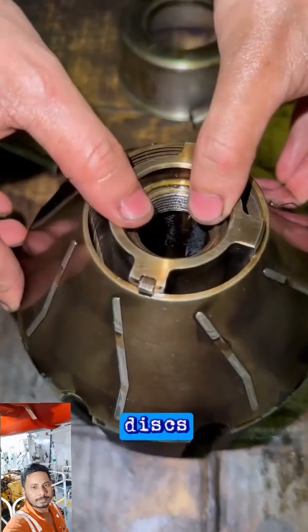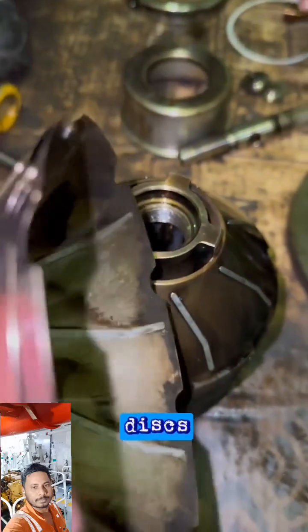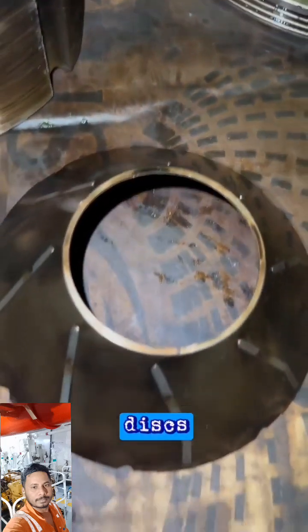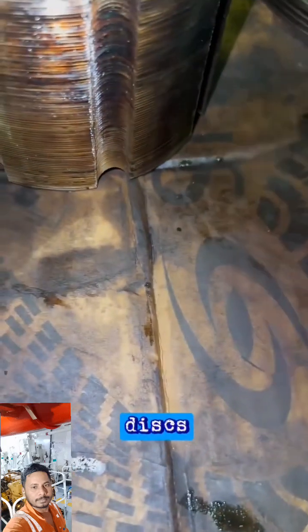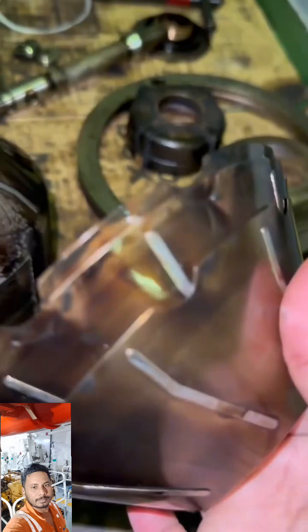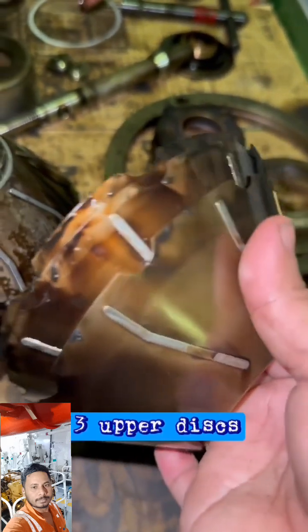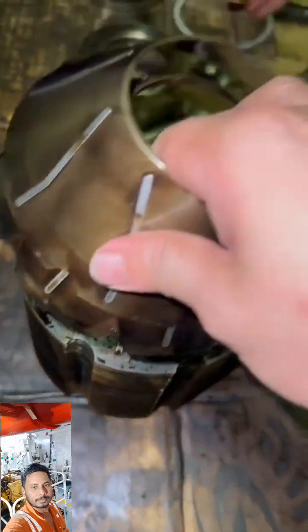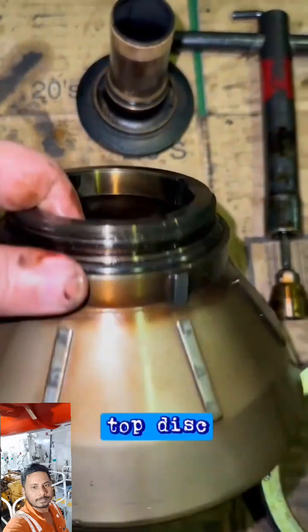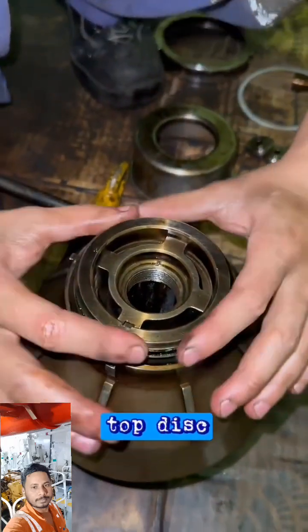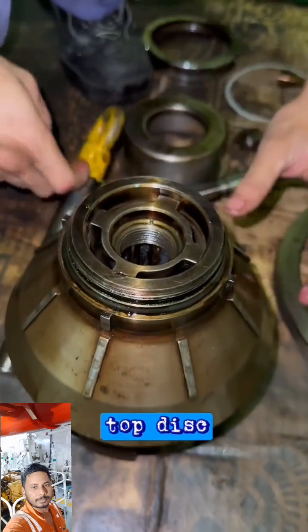Discs, divide the space within the bowl into small passages in order to break the bulk of oil into smaller quantities, which is confined to pass through the small passages provided by the arrangement of discs. The upper discs. The top disc, used to cover the pile of discs and maintains the tightness of the discs inside the bowl.